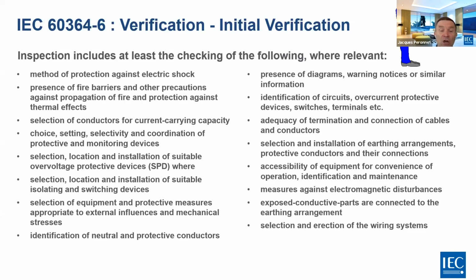The identification of neutral and protective conductors. In IEC, the protective conductor is green and yellow, whereas in the NEC it is only green, but this is exactly the same principle. We also have the presence of diagrams, notices, wiring notices, and similar information. You have to make sure that the identification of circuits is correct. The overcurrent protective devices, switches, and terminals also are correctly identified.